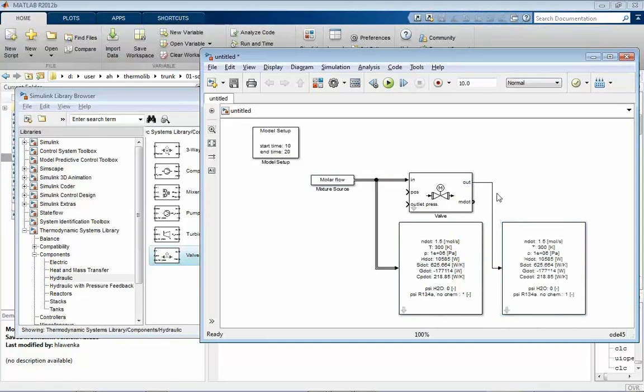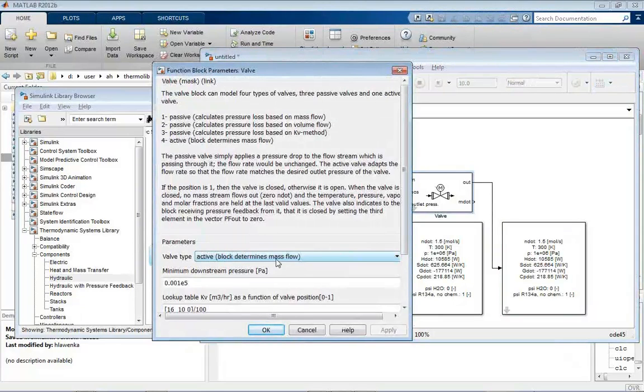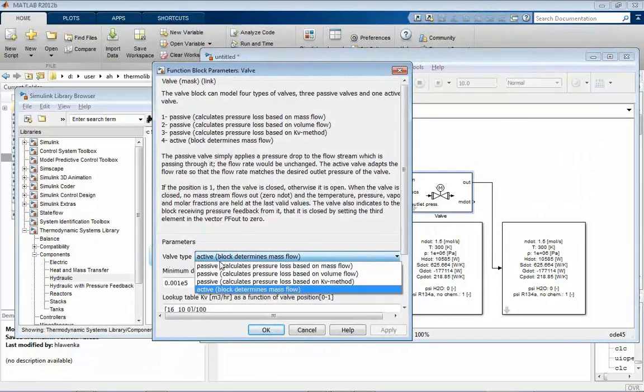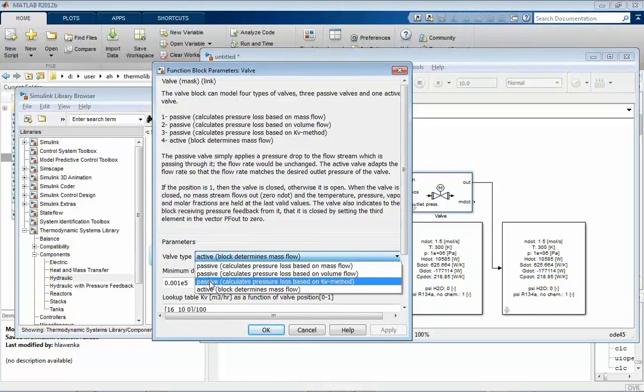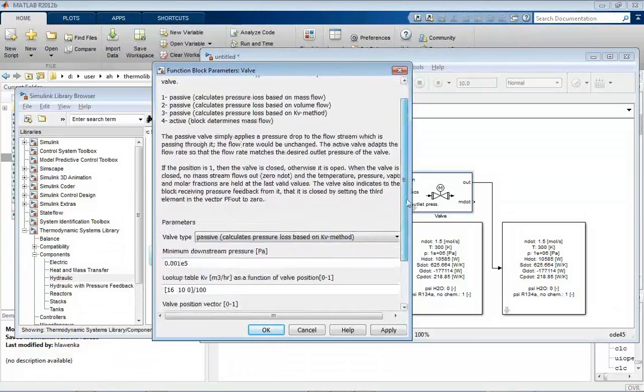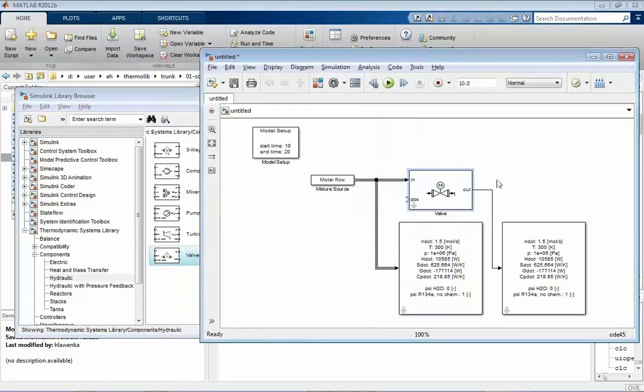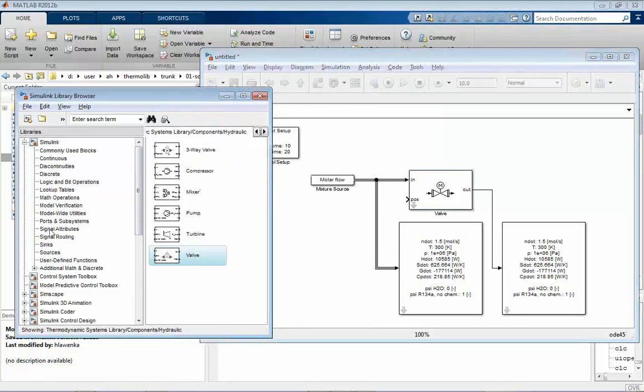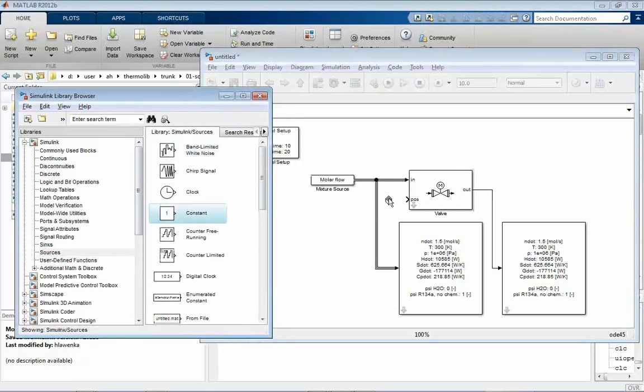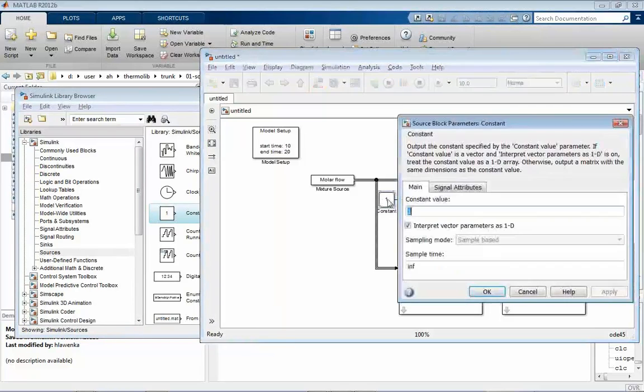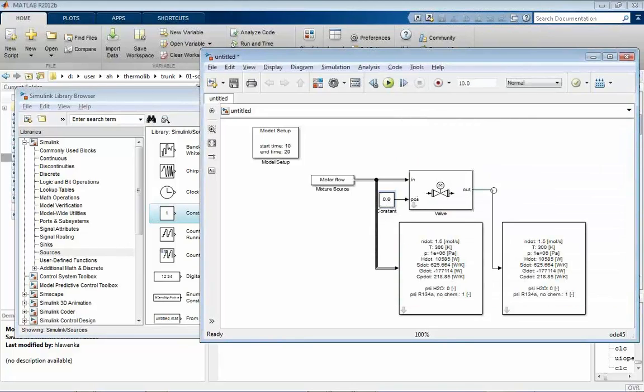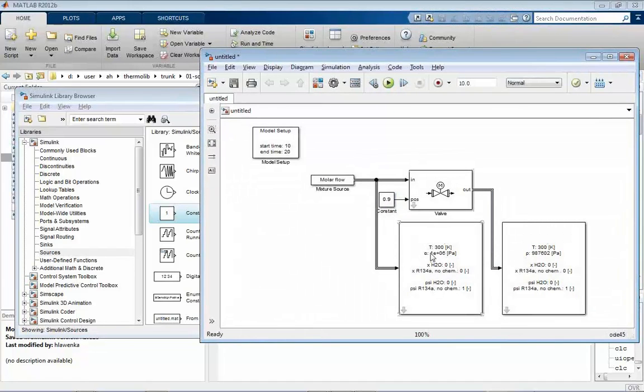At the output of the valve you can visualize the current state. For the direct method, you choose a valve type — you have options to choose between passive and active modes, and for the direct method you always choose a passive mode. Here we choose passive mode with the Kv method and set a Kv value accordingly. We also need the valve position, so we add a Simulink source and define the position to be 90% closed. If you run the simulation you see that from the 10 bar the pressure drops a little bit — we have 9.8 bar at the outlet of the valve — but the vapor fraction x value is 0, so we still have all liquid.